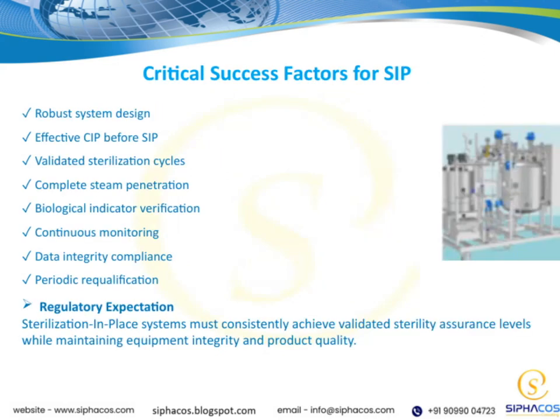When it comes to sterilization in place systems, several critical factors determine success. First, the system design has to be robust. It needs to handle real-world conditions without fail. Before starting, an effective cleaning in place process must be in place. Sterilization cycles must be validated thoroughly, ensuring complete steam penetration throughout. Biological indicators verify that sterilization is effective. Continuous monitoring keeps everything on track, while data integrity ensures trustworthy records. Finally, periodic requalification confirms ongoing compliance. All of this meets regulatory expectations for consistent sterility and product quality.